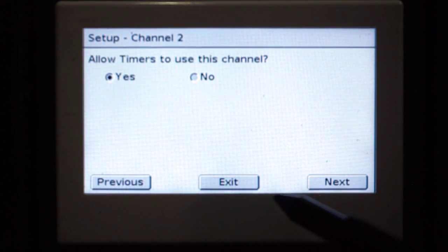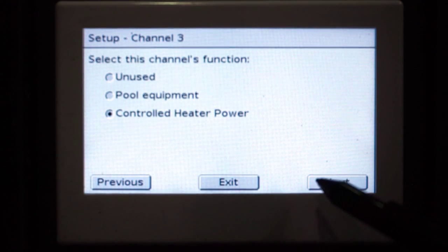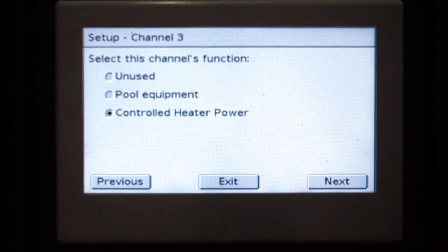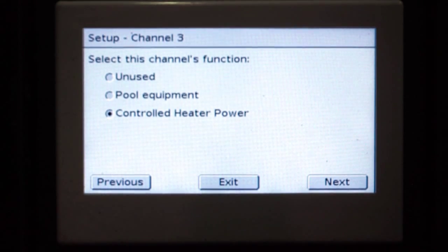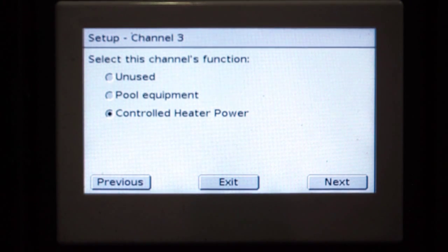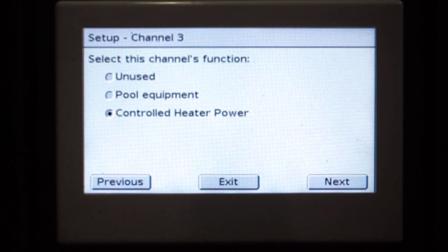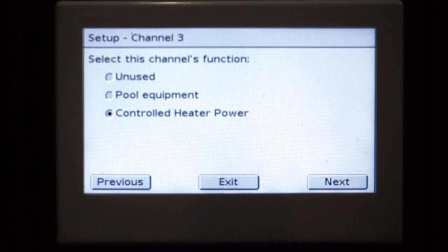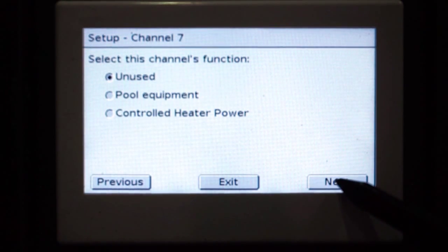Channel 2 is our cleaning pump for our in-floor system. Channel 3 is our controlled heater power. Now for heat demand, you can either have a water pump to activate a heat pump that is in constant power, or you can have a 10 amp 240 volt or 15 amp 240 volt as per our channel allowance for a heat pump connection. So that means a heat pump or a water pump will plug into a power point and this will be turned on via our controlled heater power. No other channels are being used in this configuration.